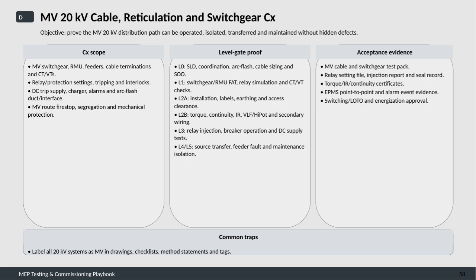We also look at relay and protection settings, ensuring that tripping and interlocks function correctly. Additionally, the DC trip supply, chargers, alarms, and arc flash interfaces are tested. The scope further includes physical protection such as fire stops, segregation, and mechanical safeguards along the MV route.